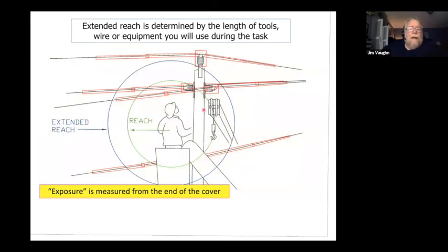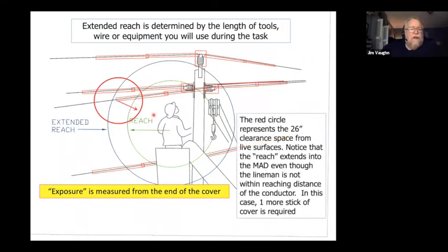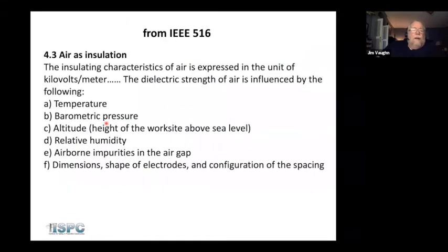If I'm in a bucket and I'm working in an energized environment, and maybe I'm hanging a transformer on this pole coming up from this boom, then MAD starts here. This is my reach, and maybe whatever tools or jumpers I'm working with might be this extended reach. But look what happens when I put a circle there that represents the sphere or the plane of the energized exposure, the MAD. And you can see here that this lineman is well within reach of the MAD.